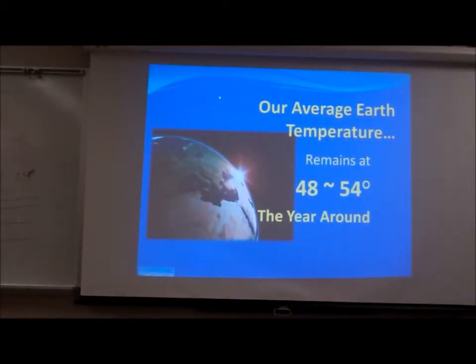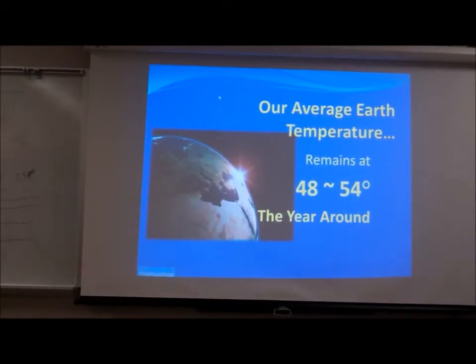The earth itself is really a heat soak. Underground, about 50 feet down here in town, it's about 50 degrees year-round. The typical coldest temperature is about zero, and the typical hottest temperature is about 100, so the earth represents a median annual temperature — that's really all there is to it. When we talk about geothermal HVAC, we're not talking about deep earth geothermal where they drill five miles down, pump water and blow back steam to run a turbine. This form of geothermal is about stored solar energy in the near earth.